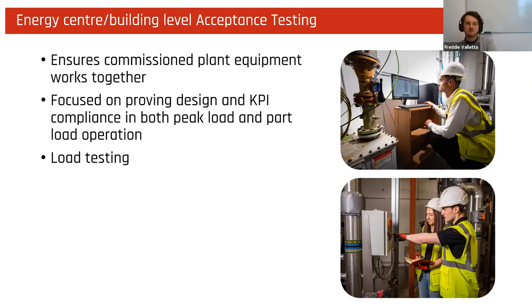As I said, at the building level, there's been a historic focus on commissioning your individual components separately, with the assumption that the DesOps and control system will tie all of the operation together, with occasional tests proving that the system can actually operate stably at its peak load. However, as heat networks are dynamic systems, the plant equipment needs to be proven to operate under variable and part loads, seeing as these peak loads are rarely seen on systems and only last for a matter of minutes.